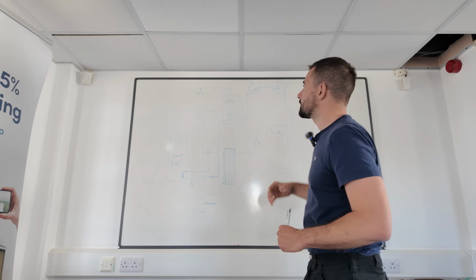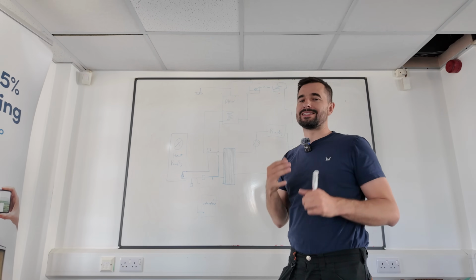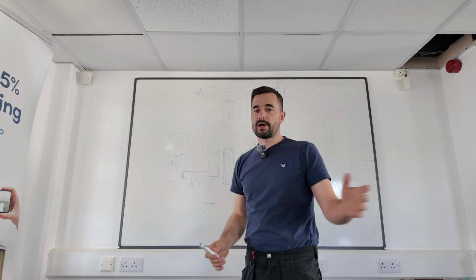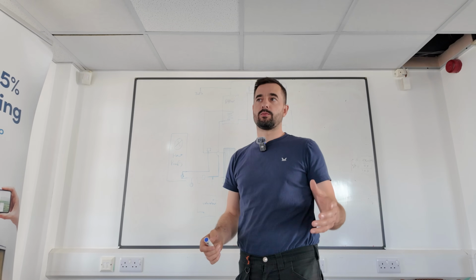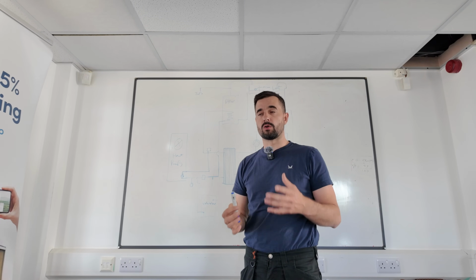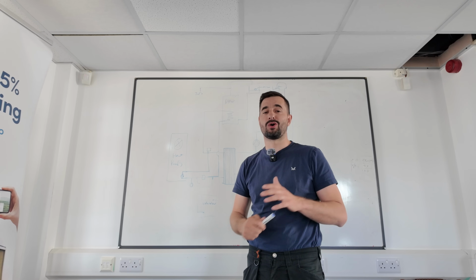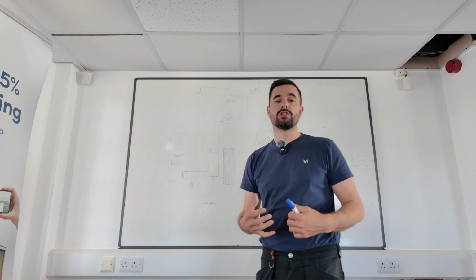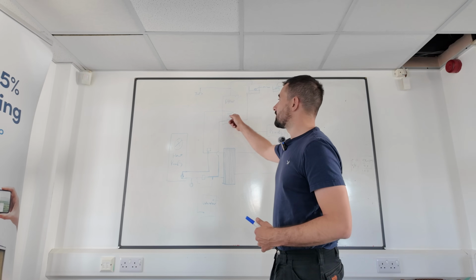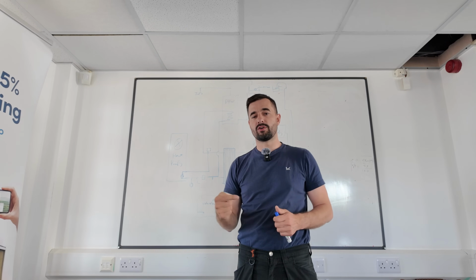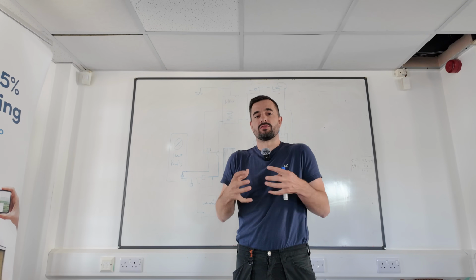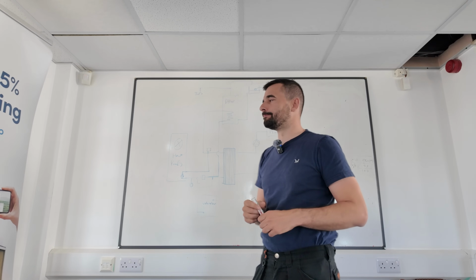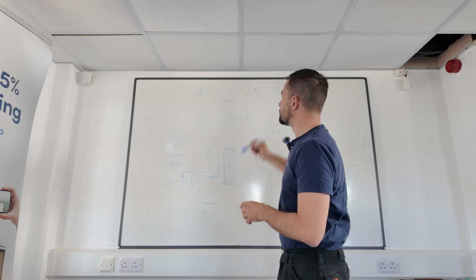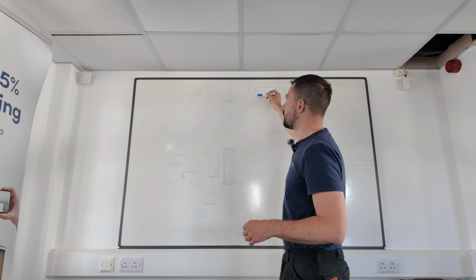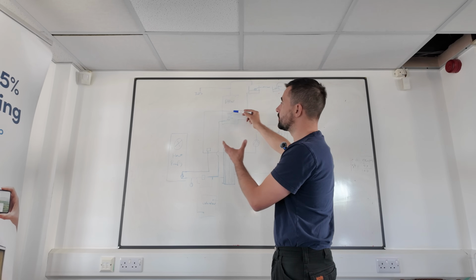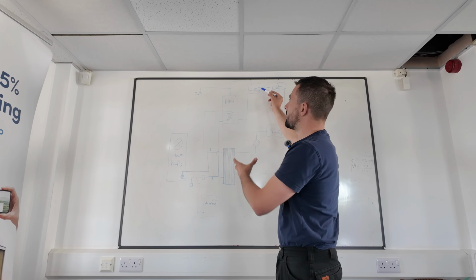Okay, the second side of it was the hot water system. The customer didn't want that pressurizing either. All the bathrooms that's in that property have old pipework and old valves that don't lend themselves to being on pressurized hot water systems. So again, if you install a new system with a pressurized cylinder, that'll typically be fed via a 3.5 bar pressure reducing valve, and then obviously it'll heat up and have a little bit more pressure than that in. So what we did was we left the existing feed and expansion tank in the loft and fed the new cylinder with the oversized coil in to be fed from that.